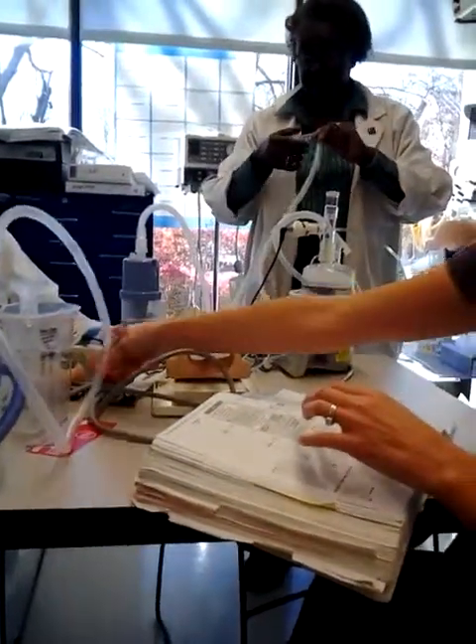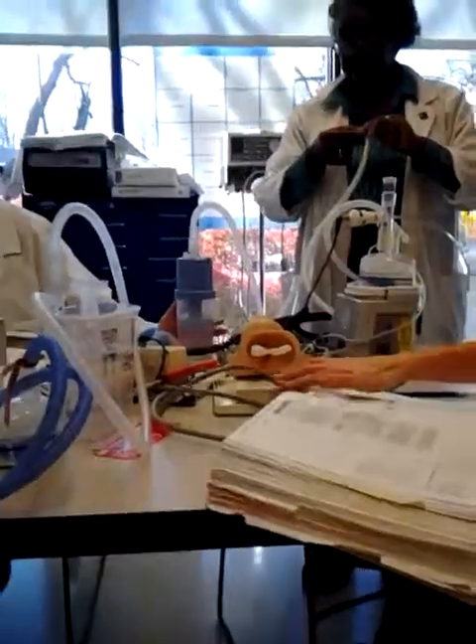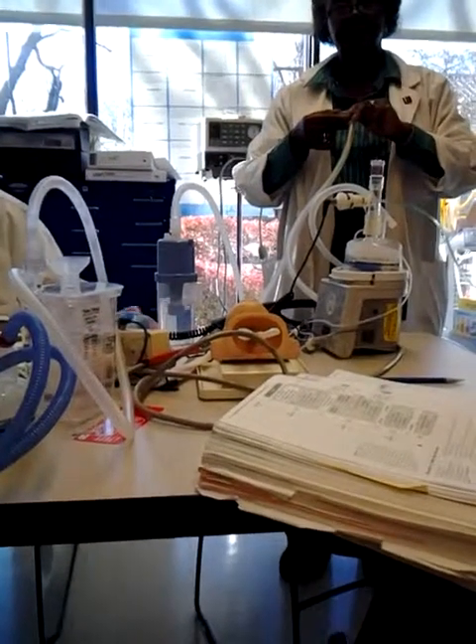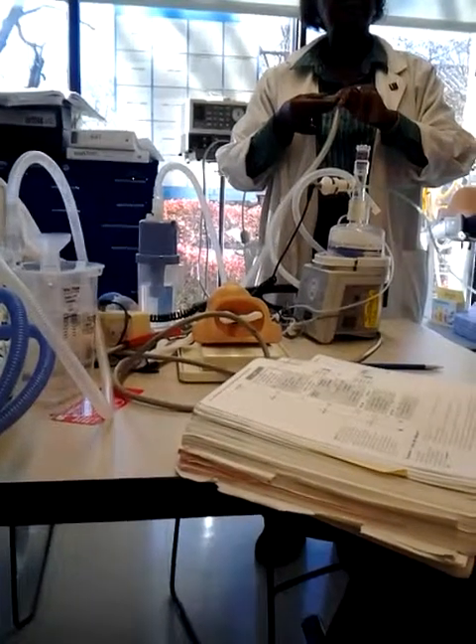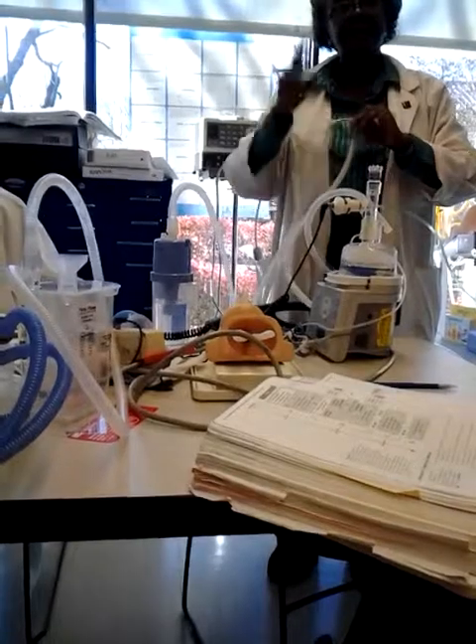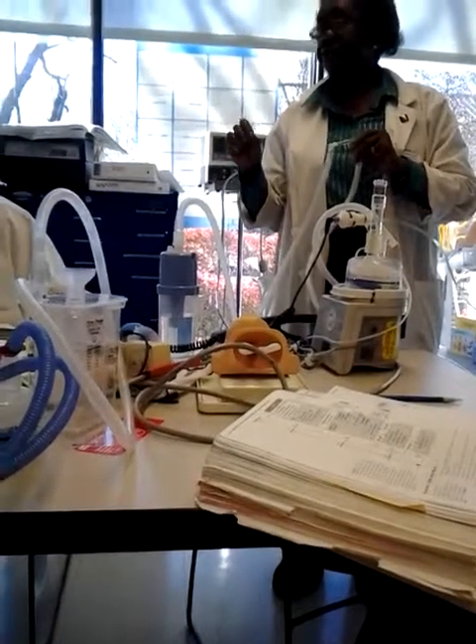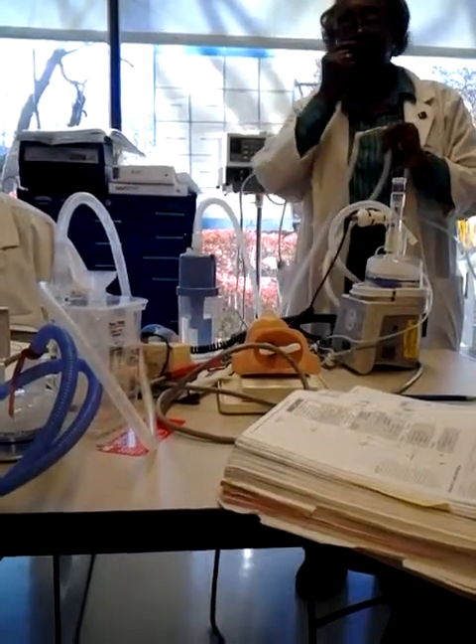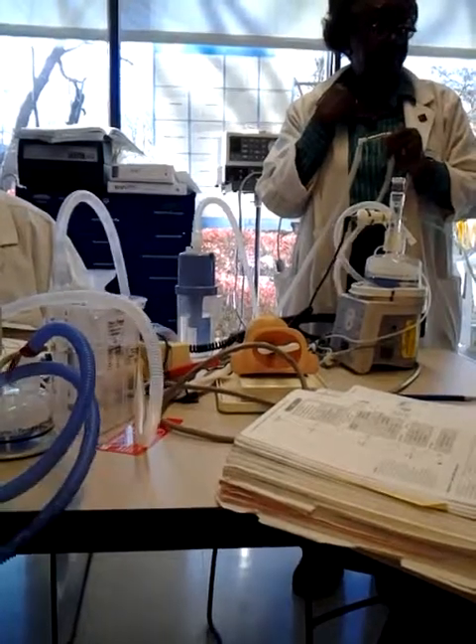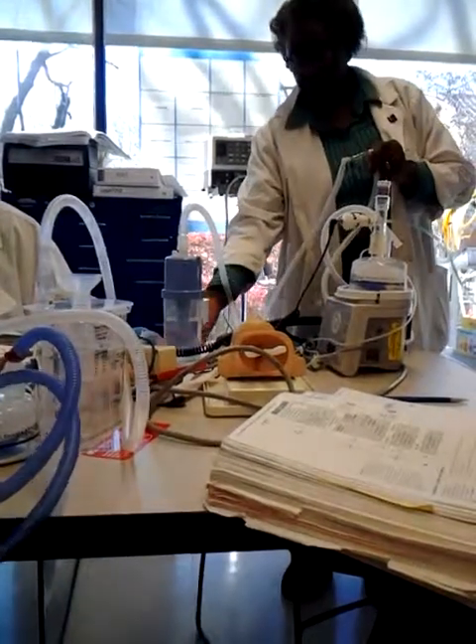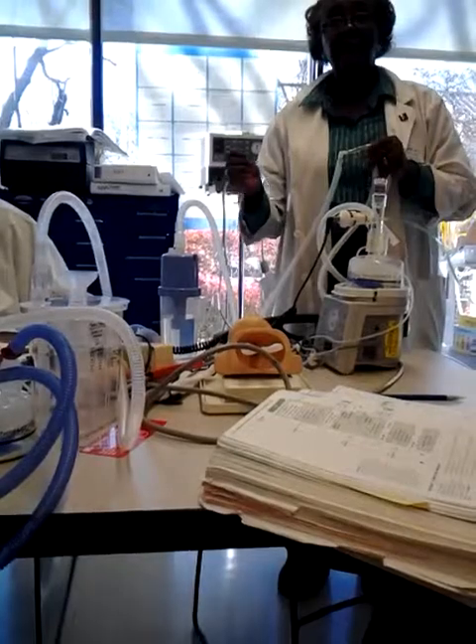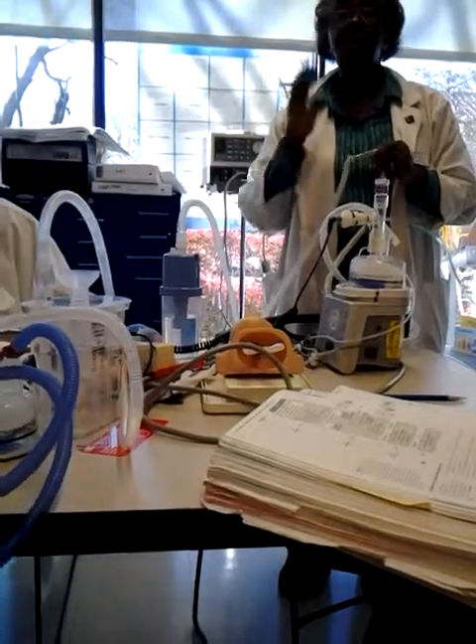Nothing's happening now, but if I occlude it, now I'm starting to get bubbles. So if you have a leak in the system, the baby isn't getting anything. Now the reason they were saying that they don't like to use this is because it doesn't have alarms. You don't know if it comes out of the baby's nose. You don't know if your water level is too low or if something is disconnected because you have no alarm.